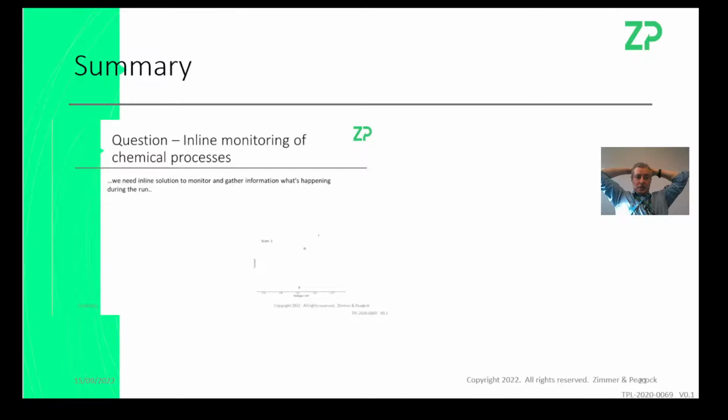We have a whole stack of flow cells, some of them with all the wetted parts of PTFE and glass, but they do work at low pressure, not high pressure. So you do have to come out of a pressure system, be atmospheric, and then you can flow into our system. So we do have those flow cells, and obviously we also do have the instruments as well.